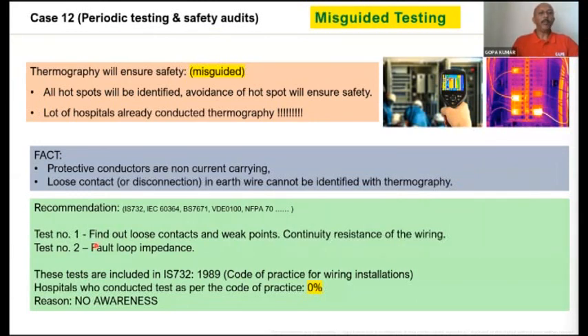So for finding out the loose contacts, you should do test number 1 in the IS 732, or test number 2, fault loop impedance. If you do these two tests, all the loose contacts can be found out. During this COVID time, I visited a lot of hospitals, and I was asking the engineers in the hospital, have you conducted the test fault loop impedance or MCB tripping? The answer which I got is almost 0%. Nobody knows this particular test. The reason is people are not aware.